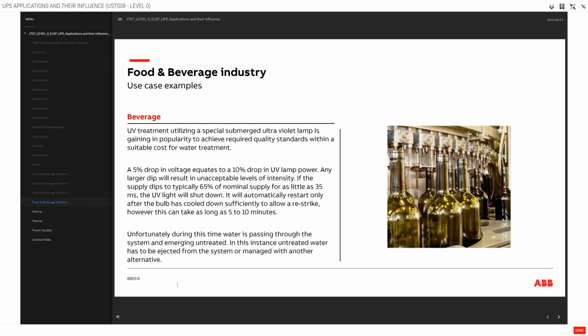Beverage. UV treatment utilizing a special submerged ultraviolet lamp is gaining in popularity to achieve required quality standards within a suitable cost for water treatment. A 5% drop in voltage equates to a 10% drop in UV lamp power. Any larger dip will result in unacceptable levels of intensity.